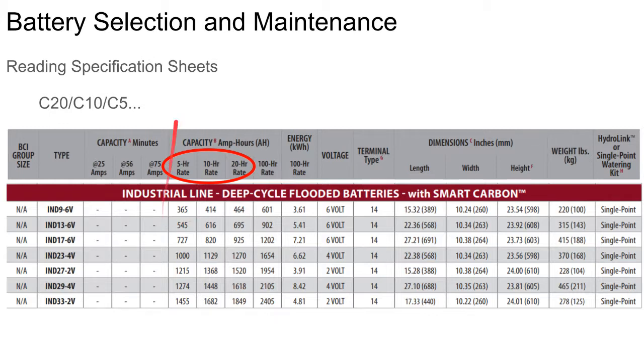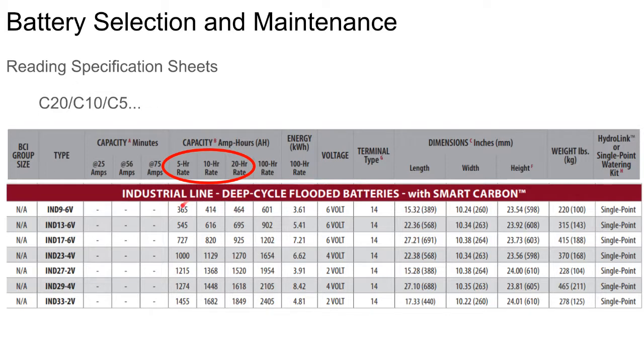And so that's where the inefficiency can creep back in, where people prefer a lithium-ion battery because you can charge it over a 2-hour window and then discharge it over a 2-hour window, and you're still at its same rated capacity. You do the same thing with a lead acid, and it begins to drop off, and the danger is, hey, I only see a 5-hour charge-discharge rate here and a 10-hour discharge-charge rate right here. I don't see a 2-hour charge-discharge rate here. What happens if I try and fully discharge a lead-acid battery in 2 hours?